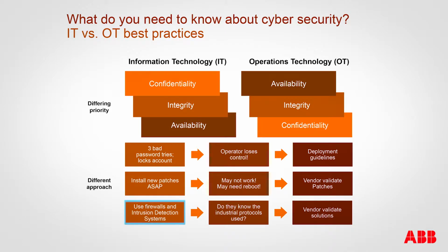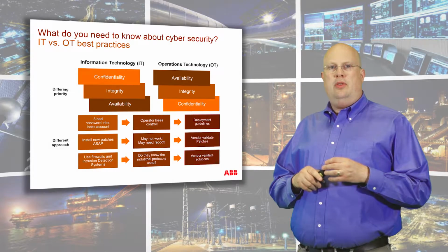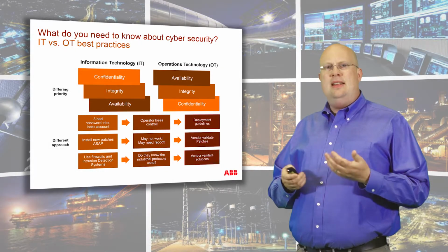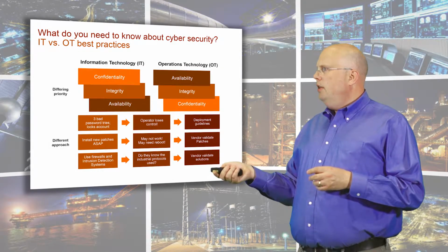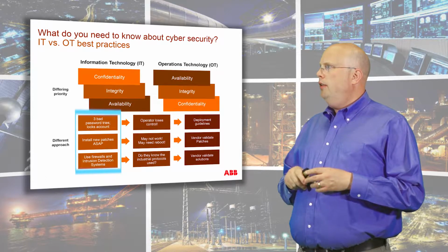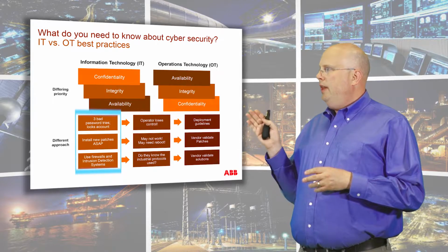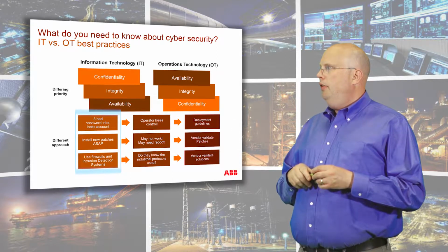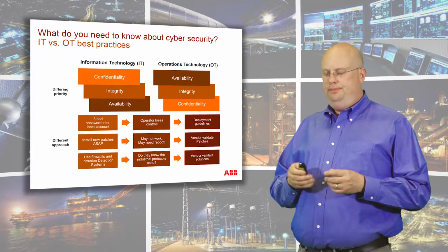Modern firewalls and intrusion detection systems, really good on an IT side. They may not be what you want to use on an operational side because they could cause trouble, they will cause increased maintenance and so on. So again, we have a couple of examples of really, really good solutions on the IT side that will have a really bad effect on the operation side.